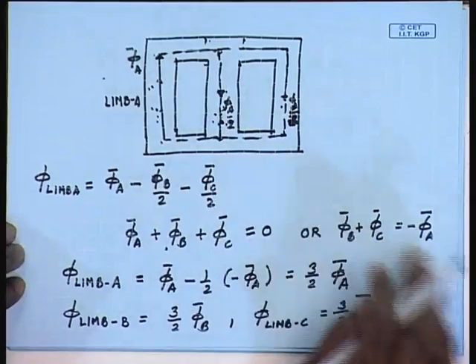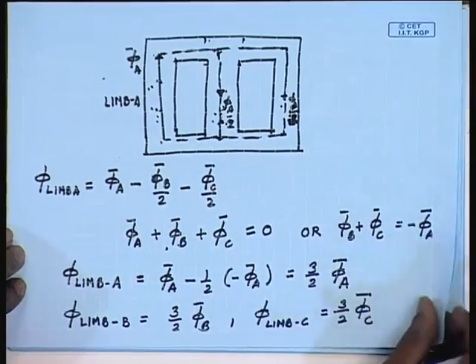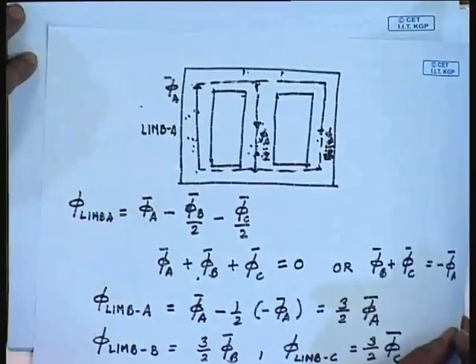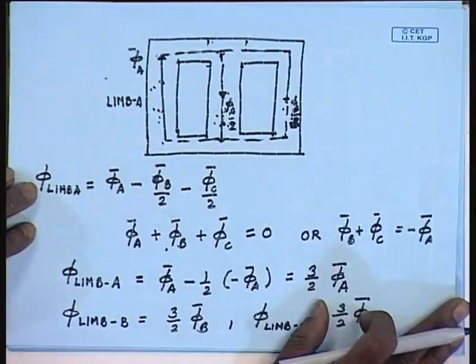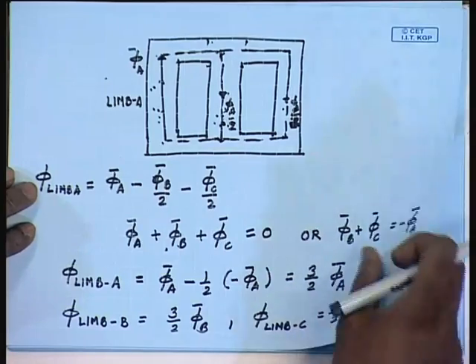The coupling can be made a little better if we use a different type of core. Incidentally, this is the core type transformer, we call it a 3-limb transformer core. More regarding construction of 3-phase transformers we will see in a later lecture, but to continue with this, this is a 3-limb core which is most commonly used. However, for very large transformers sometimes a 5-limb core is also used.